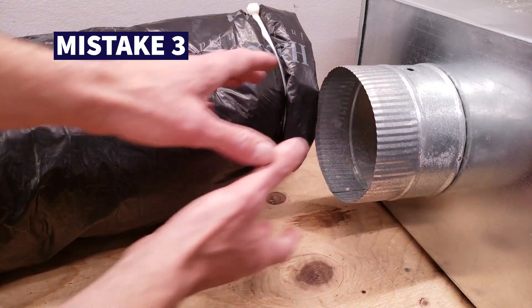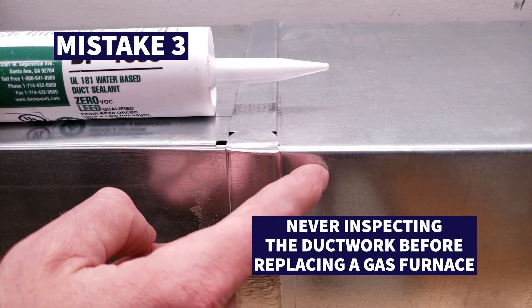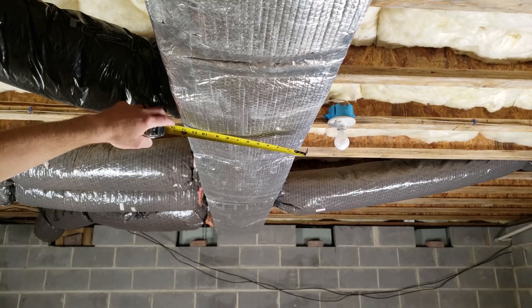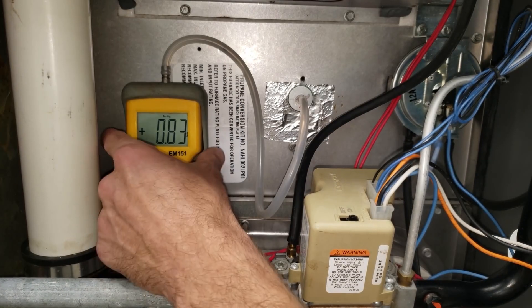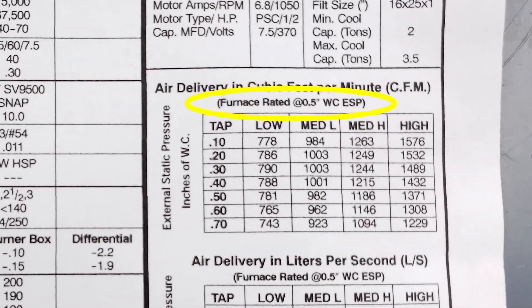Number three, which is really a huge shortcut, is never inspecting the ductwork before replacing a gas furnace. Your ductwork could be leaking — I've seen where it is completely open in the attic, sucking return air along with insulation and low-temperature air right into your new gas furnace. You could also have low insulation value wasting your heat, or ductwork that's too small to support the system. You can verify proper sizing by checking total external static pressure across the furnace from return to supply against the manufacturer's ratings.